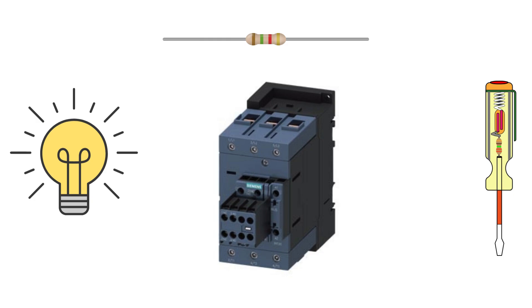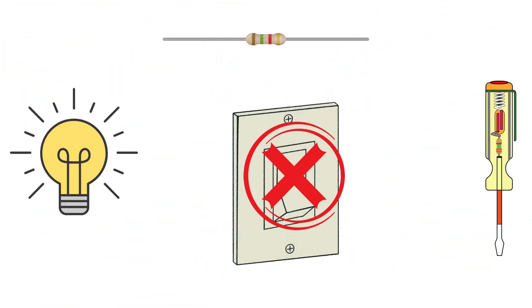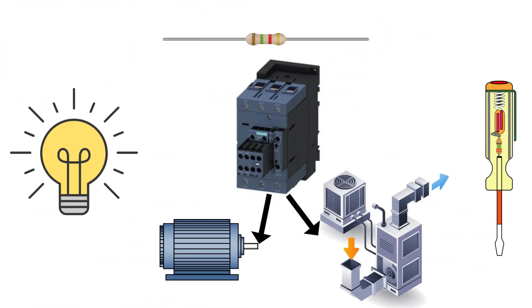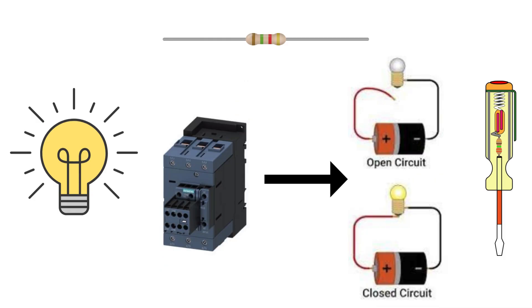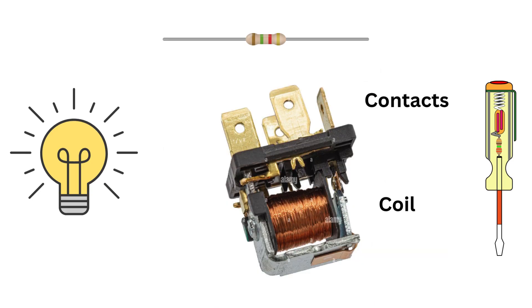Let's kick things off with the basics. What is an electrical contactor? Well, think of it as a special kind of switch that controls the flow of electricity to a device or machine. But here's the catch — it's not your typical light switch. A contactor can handle a lot more current and can control devices that require high power, like motors or HVAC systems. A contactor is essentially a device that opens and closes electrical circuits. It has two main parts: the coil and the contacts. The coil is like the brain of the contactor. When you send electricity to the coil, it generates a magnetic field and pulls the contacts together, which closes the circuit and allows power to flow to whatever you are controlling.